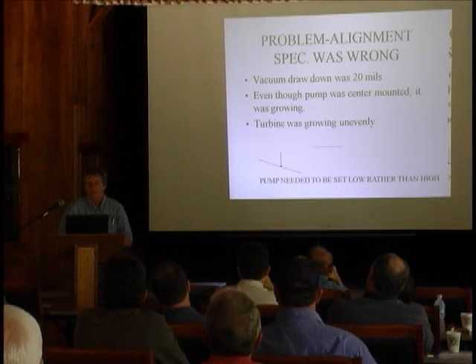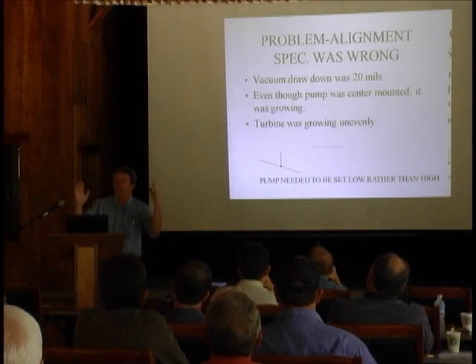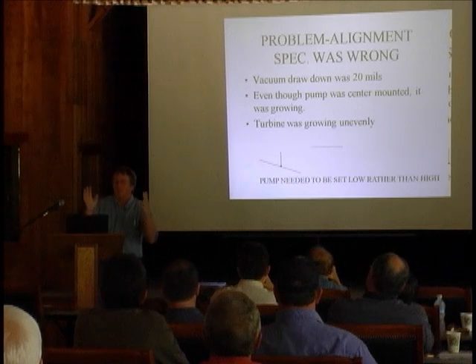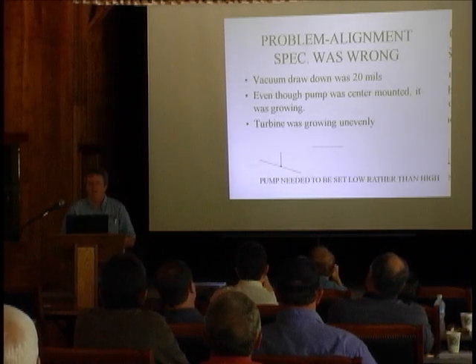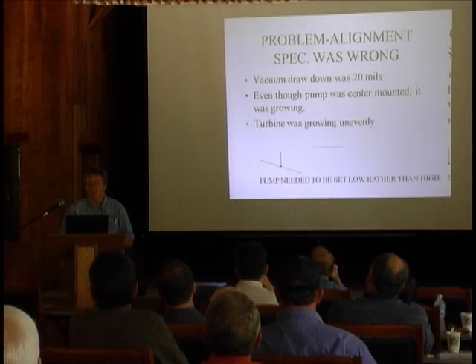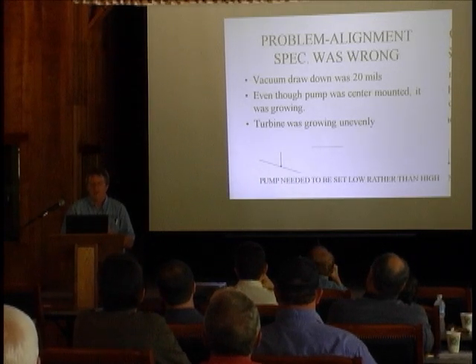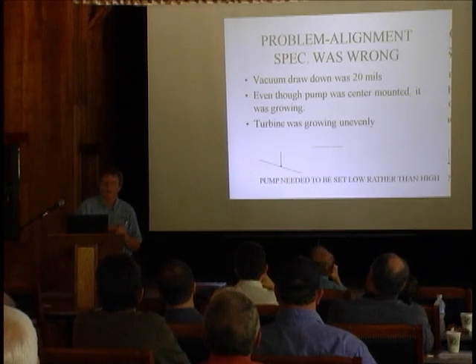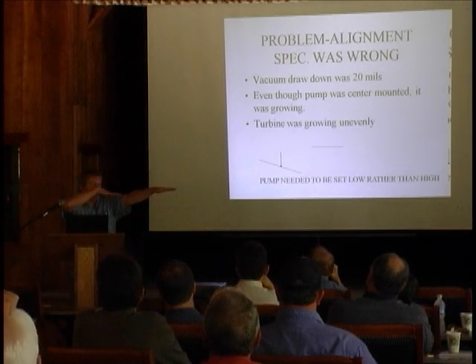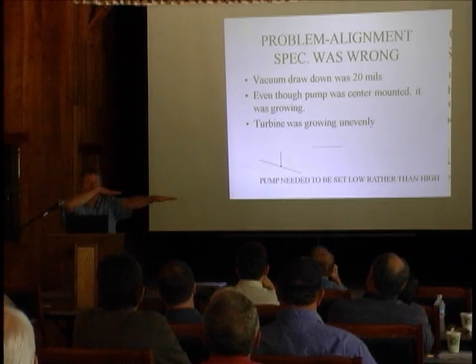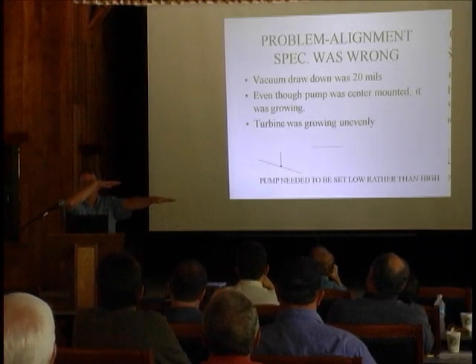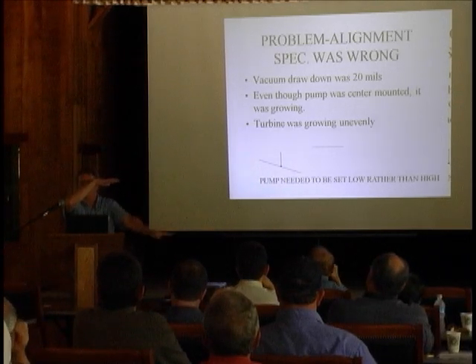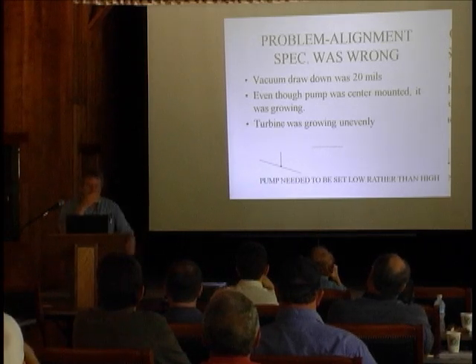Well, it doesn't, but you've got your supports, and if they heat up, it does indeed raise it a little bit. So I calculated it out, and I said, your pump's rising, and the turbine is more than likely growing unevenly too. So what they had here, they had set it up where they said the turbine's going to grow more than the pump, so boom, they set the turbine here. They said the pump's not going to grow, but it did. They didn't take into account the turbine vacuum, but it does. So this is the situation they had.